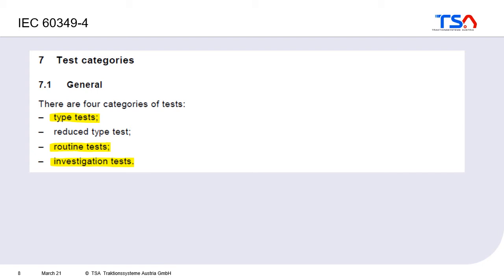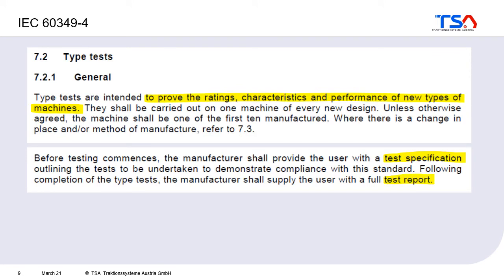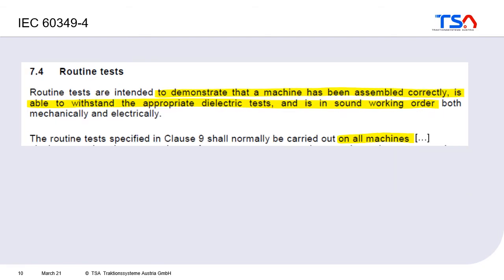Regarding tests, there are two basic types: type tests and routine tests, with optional investigation tests for additional information. The type test is done on one machine of every new design and should prove the ratings, characteristics, and performance of that new machine type. A test specification should be sent to the customer before tests begin, and a full test report is provided afterwards.